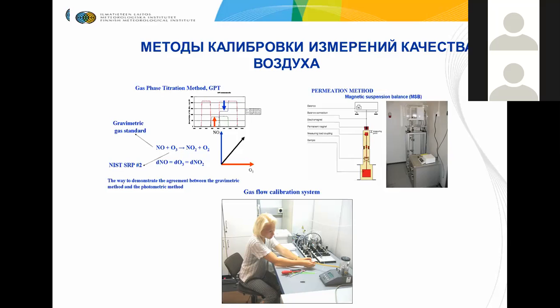So basically you cannot buy this kind of low flow calibration systems from a shop. So we have, for example, built this system by ourselves in our laboratory and demonstrated, of course, the traceability of the system, and it's also an accredited system. It's the highest standard also for these low gas flows in Finland. So it's the primary standard for Finland for these low gas flows. And one system is the permeation method also that is used in our laboratory. That's also based on gravimetry. So it's very important to have also very high accuracy gravimetry, as you can understand.